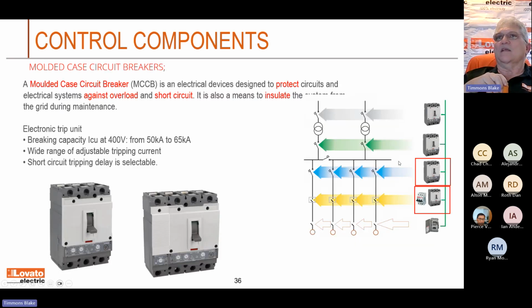Okay. And again, in the big picture, you can kind of see where these reside over here on the far right. Okay, molded case circuit breakers, and these things will have this 65 kA circuit rating. And everybody says, well, why can't you just use a regular circuit breaker? Well, the molded case breakers will have these higher short circuit ratings. Okay, so if you get a dead short, it blows up. You've got some ratings on there to keep an eye on to guide you accordingly.